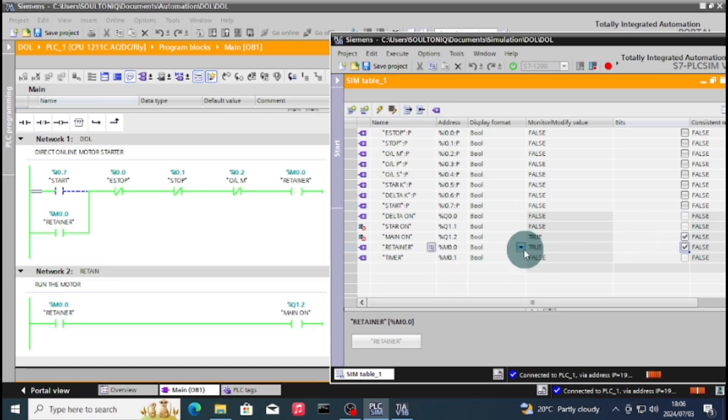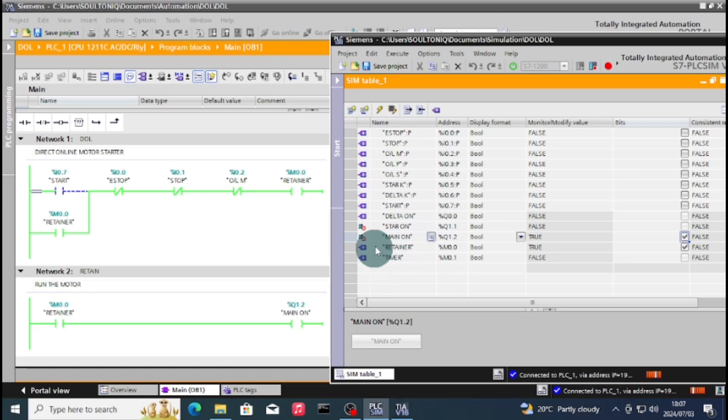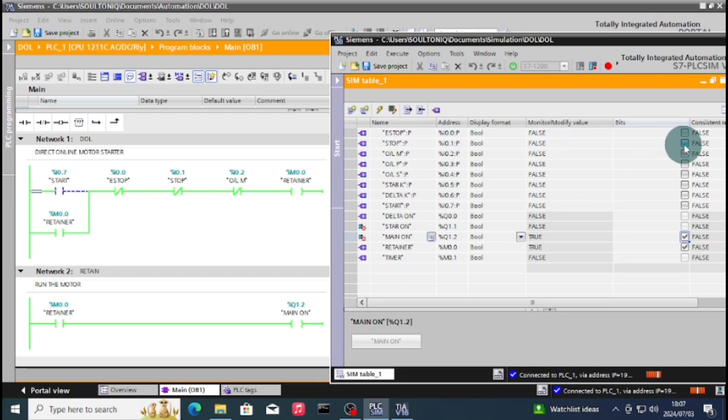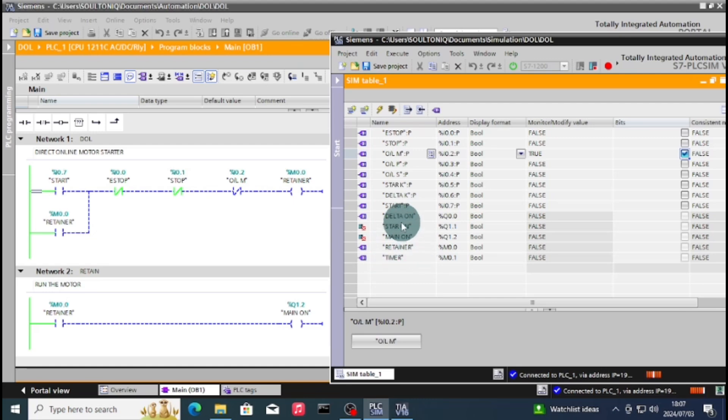So as you can see, our retainer is keeping our circuit on all the time, so that even if you release the start, it continues to run. Because our start is a push button, the circuit will only stop if the overload is tripped or the stop is pressed.